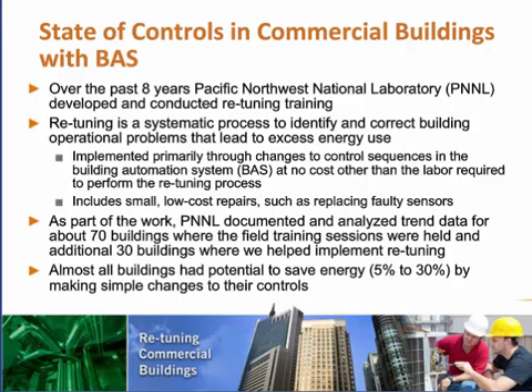Because we use trend data, we can identify things you normally wouldn't see just by walking through a building. In that sense, we can identify issues that a typical retrocommissioning agent wouldn't catch during a walkdown. Typically we collect 2 to 4 weeks of data for that analysis. So comparing our retuning approach to retrocommissioning, you can consider it retrocommissioning light, focused primarily on operational aspects and leveraging data from the building automation system.